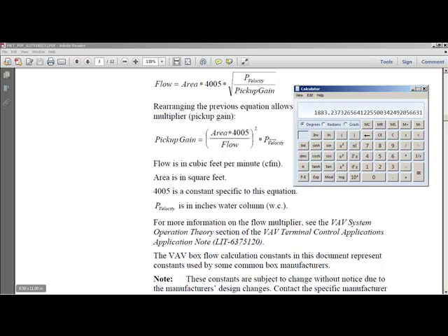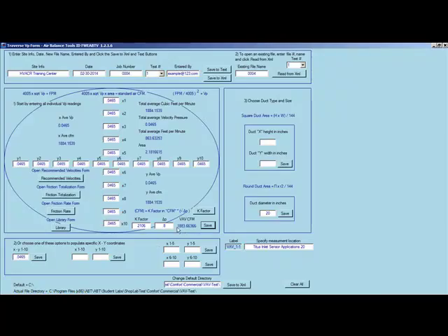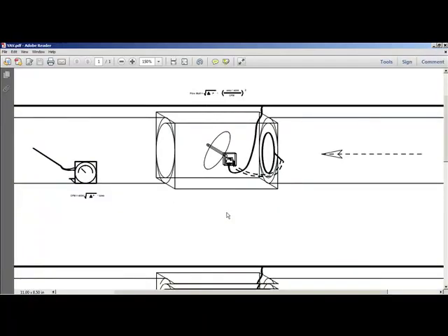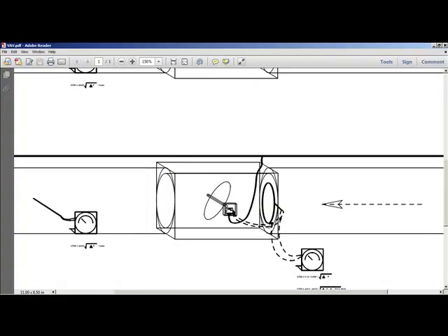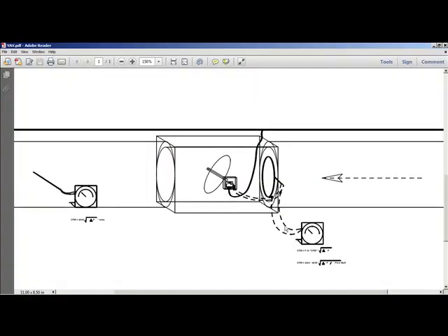Now this calculation gives us the same calculation of 18.83 for a 20-inch Titus inlet sensor application with a K factor in CFM of 2106 with a differential pressure of 0.8.